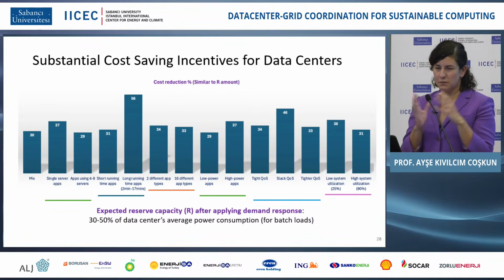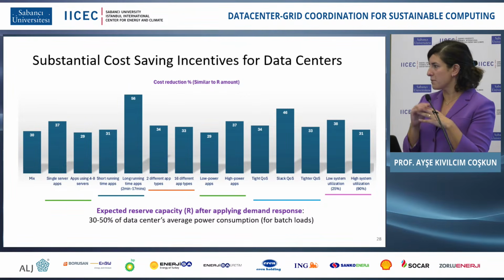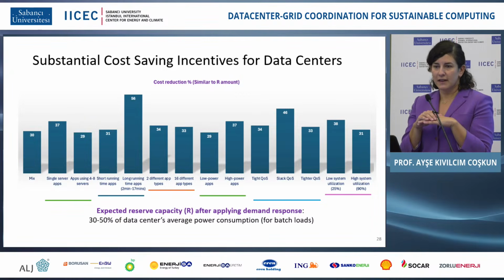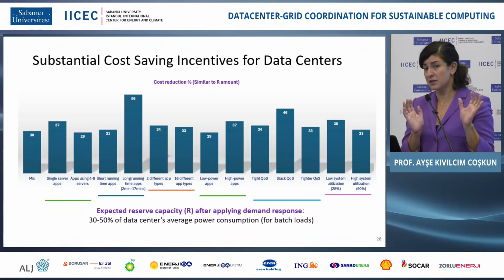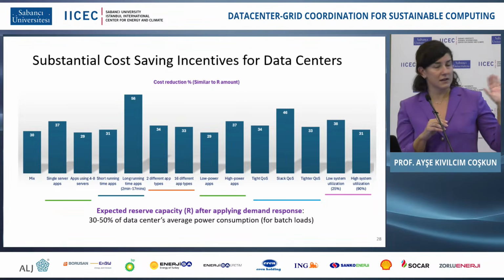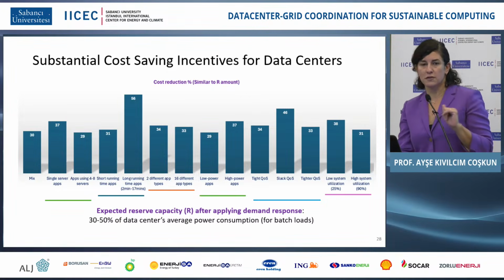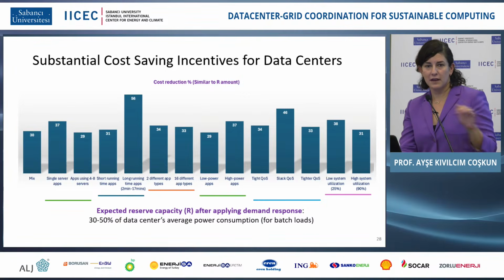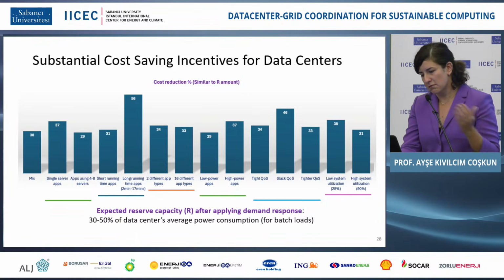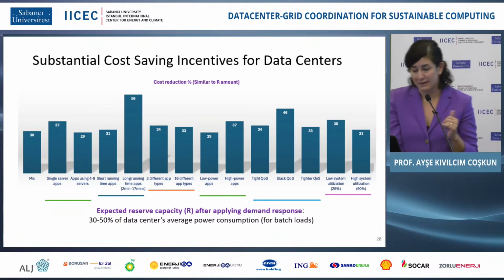So what does that mean? If I'm consuming on average 10 megawatts, then I can give 3 to 5 megawatts back as flexible reserves to the grid. That's a very substantial number. And actually, the incentive for doing this is also very strong for data centers, since they can potentially get 30 to 50% back.